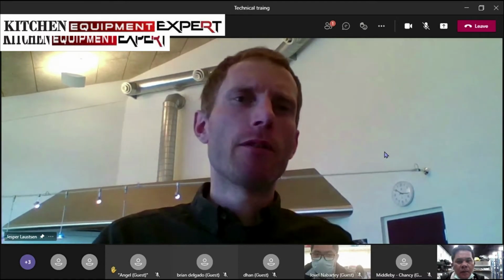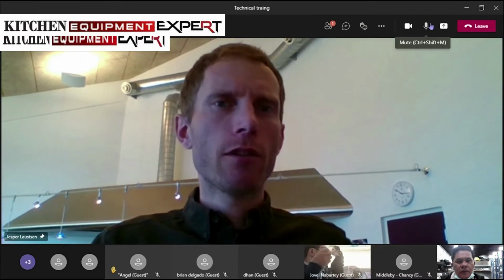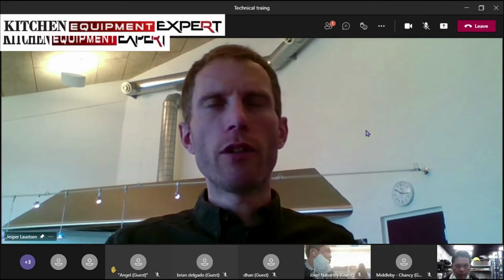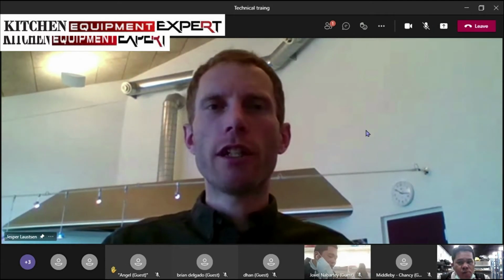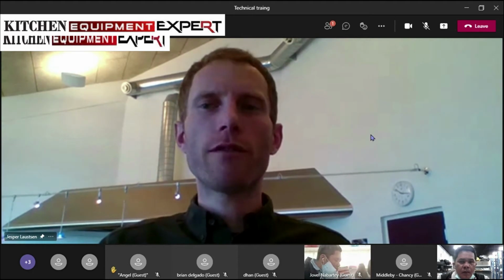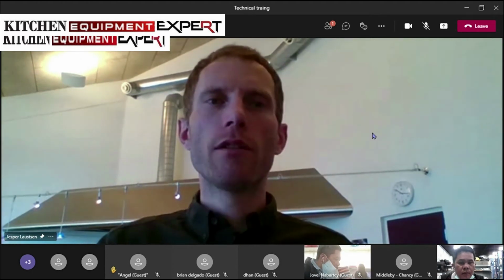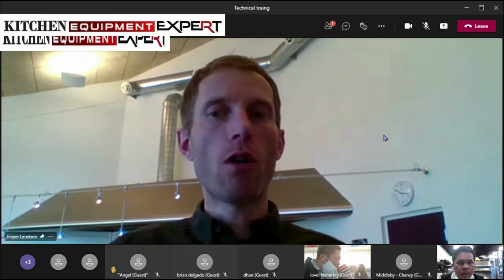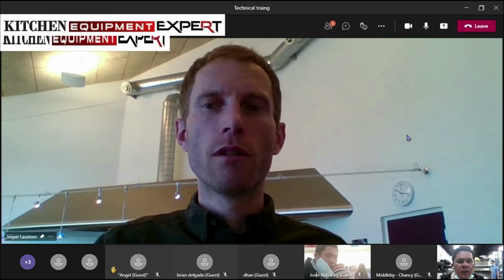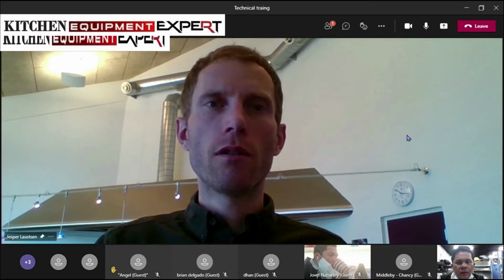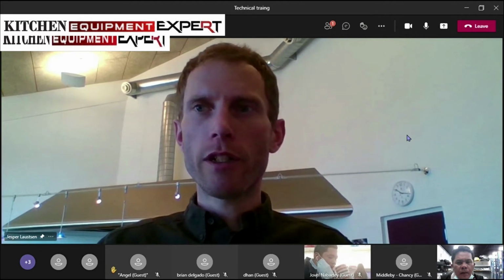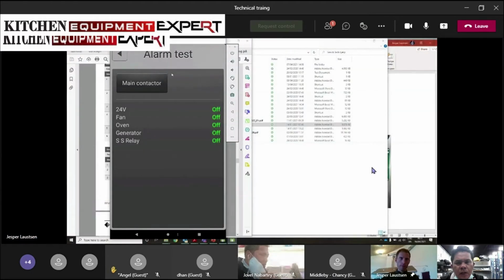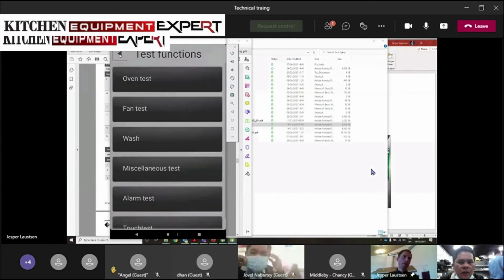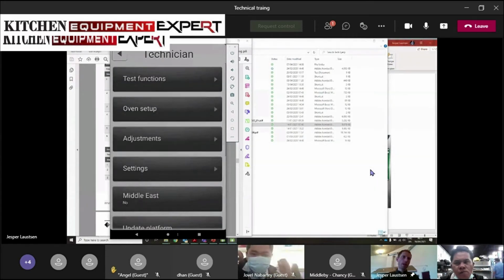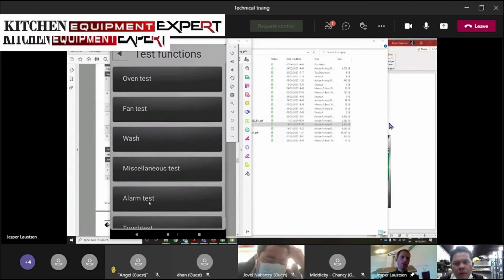Okay, that's a bit strange, I think. Let me just check a bit. So when you go from the technician menu to test functions and alarm test, you will have 24 volts off or on. I don't see that on or off. Okay, let me share my screen. I'm very curious because I already replaced all the parts, except the fan motor. If you go into the technician menu, you go into test functions, and then you'll find the alarm test.